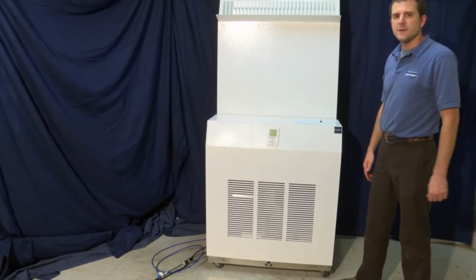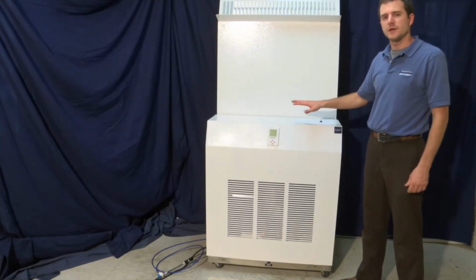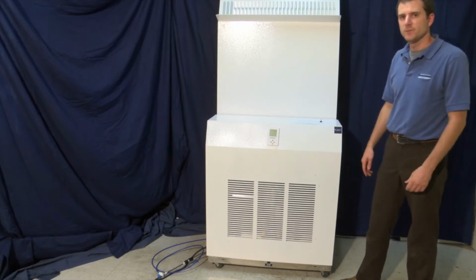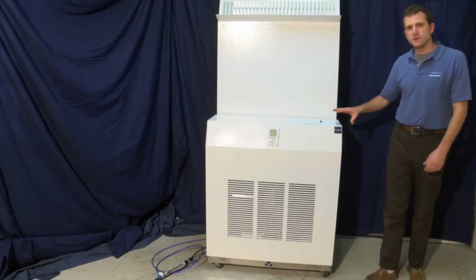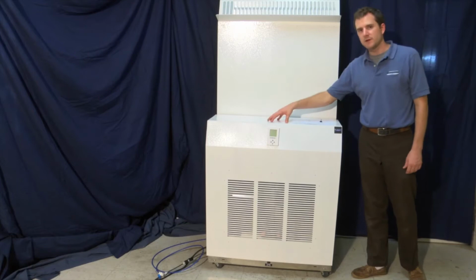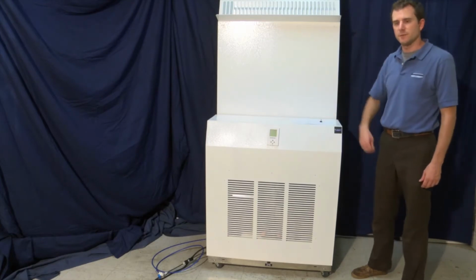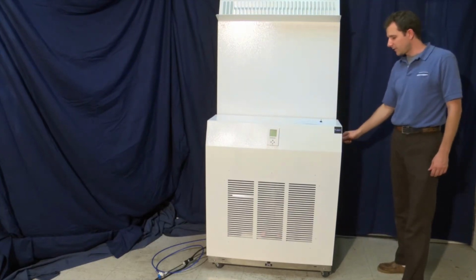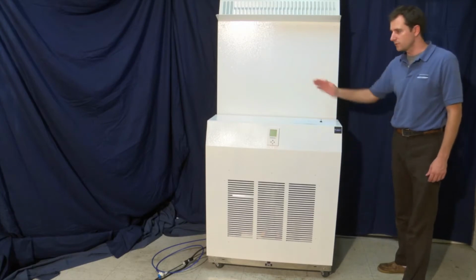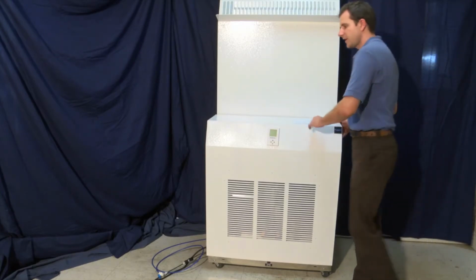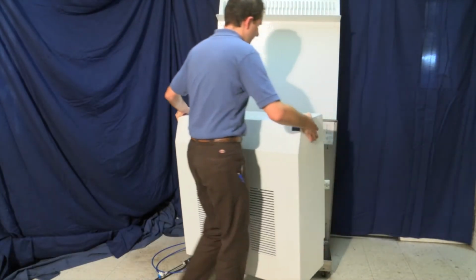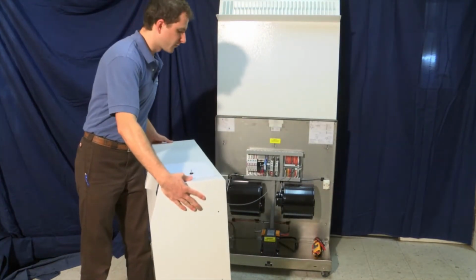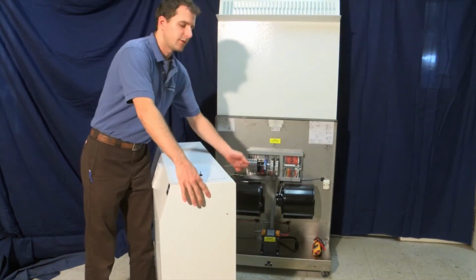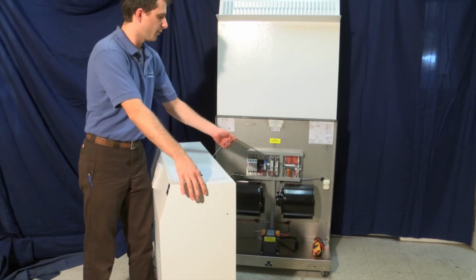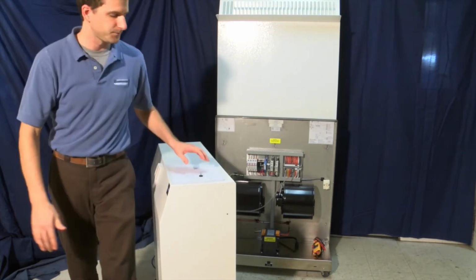We would like to take this opportunity to go over some troubleshooting tips for your MistFree series humidifier. Any troubleshooting done in the MistFree series will require you to remove the fan cover to get at the interface plate beneath. You can remove the fan cover by removing the 6 thumb screws, 3 on each side, and removing the fan cover itself. Note the 3-foot cord between the humidistat and the terminal block. Be sure not to pull or strain on this cord.